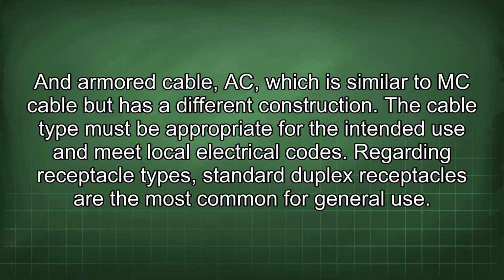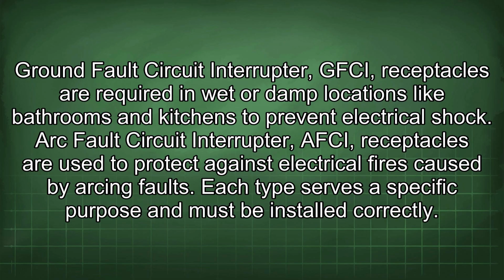Regarding receptacle types, standard duplex receptacles are the most common for general use. Ground fault circuit interrupter, GFCI, receptacles are required in wet or damp locations like bathrooms and kitchens to prevent electrical shock. Arc fault circuit interrupter, AFCI, receptacles are used to protect against electrical fires caused by arcing faults. Each type serves a specific purpose and must be installed correctly.